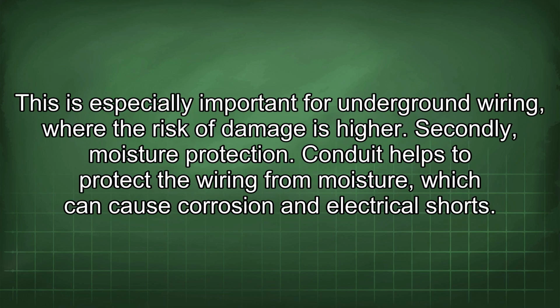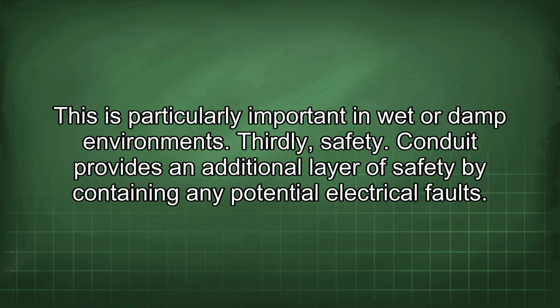This is especially important for underground wiring, where the risk of damage is higher. Secondly, moisture protection. Conduit helps to protect the wiring from moisture, which can cause corrosion and electrical shorts. This is particularly important in wet or damp environments. Thirdly, safety. Conduit provides an additional layer of safety by containing any potential electrical faults.